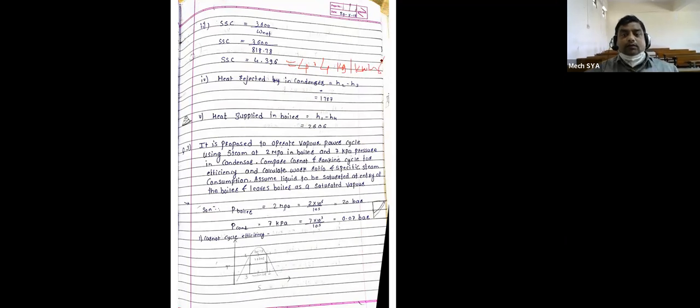Okay, specific steam consumption means what? It calculates the rate per electrical unit, which is very important. Specific steam consumption is 4.4 kg per kilowatt hour. So in this condition, if we have to develop 1 unit, then 4.4 kg of steam is required. Then to generate 1 kg of steam, how much fuel is required, that we are going to find. And depending on those calculations, we give the rate to other companies when we want to sell the electricity from generation.